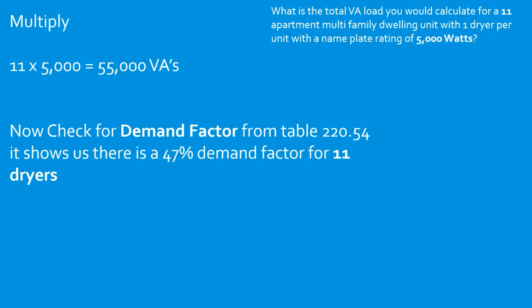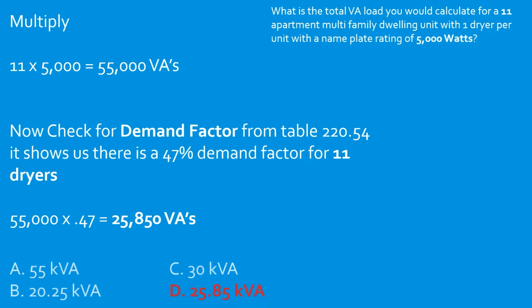First, you start on the left-hand side and find your number of dryers. Now we're going to come over and tee off with our percentage. In this case, it's 47% for 11 dryers. So what we do is take our total VAs and multiply it by the demand factor, 0.47. That's going to give us a new total load calculation of 25,850 VAs. And we're going to select D.